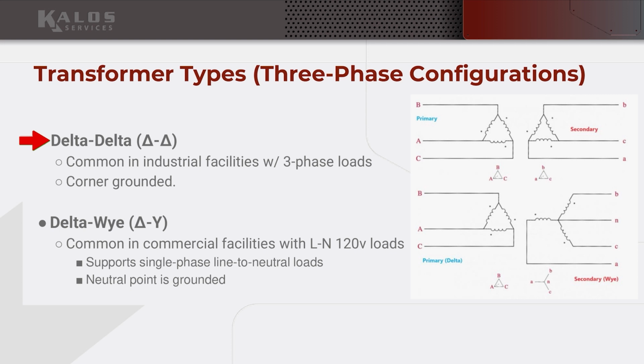Three-phase loads will still not function, but two-phase loads across A and C will continue to function, and to some degree from A to B, loads or single-phase loads will continue to function, although not optimally. But there is some benefit to delta, where if you lose a leg, you don't lose everything. But they're not friendly to 120 volt loads.